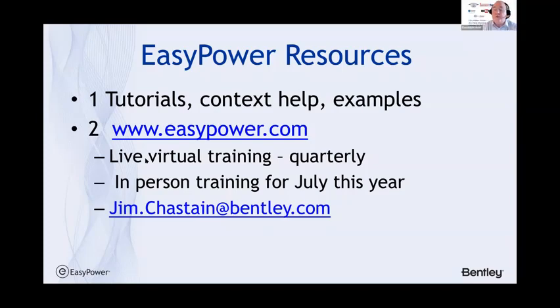Okay, question. What do you think about keeping incident energy under control by calculating adequate transformer impedance at the very beginning of the project? That's a little dicey. Again, what you're doing is you're looking for not the worst case, but you're looking for the best case in terms of PPE results. And what if you're wrong could be a disaster, only maybe less often than what you were shooting for. I guess I wouldn't encourage that. So the solution is to calculate with worst case and best case, and then make a decision on how much risk either involves.